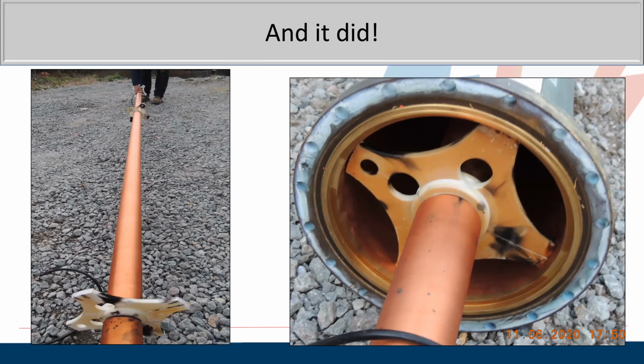So it was a disaster waiting to happen, and it did. I told the client exactly where this was - it was at about 937 feet. They took it apart and found that this O-ring was not installed properly, and it slipped down onto the Teflon insulator and caused this arcing every once in a while. It wasn't consistent - it would just arc every once in a while.